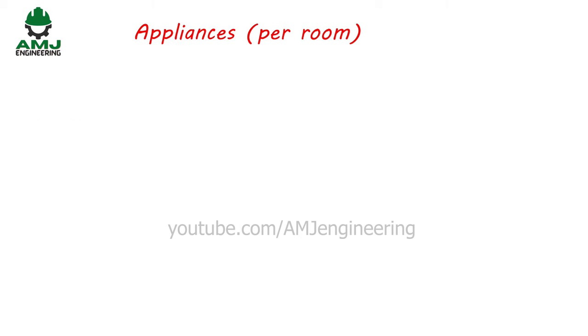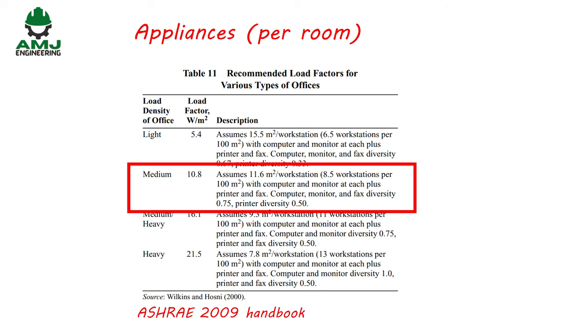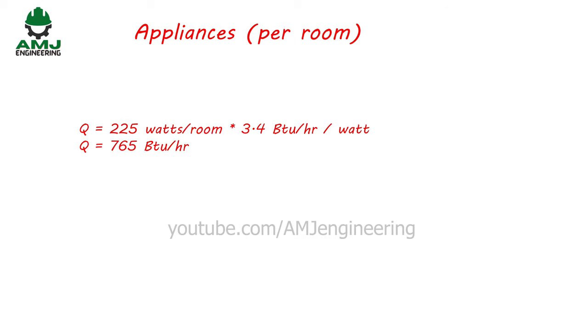The last step is to calculate the heat load from appliances. Per ASHRAE Fundamentals 2009, Table 11, offices with medium load density have 10.8 W/m² (approximately 1 W/ft²). For 225 ft² per room, that is 225 watts per room, giving Q = 765 BTU/hr per room.